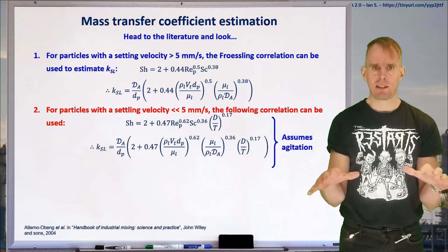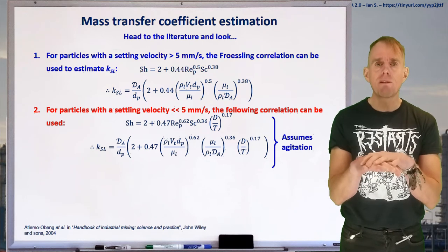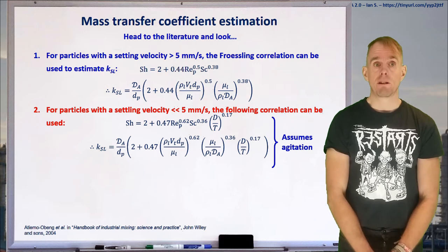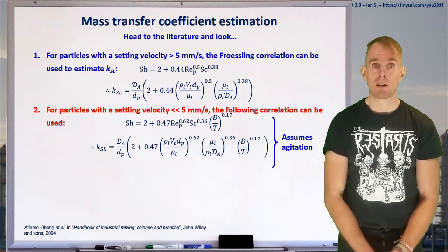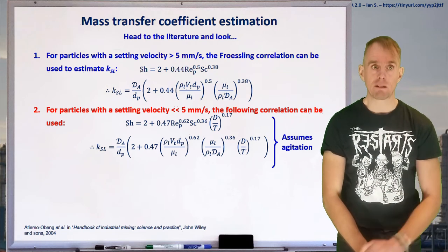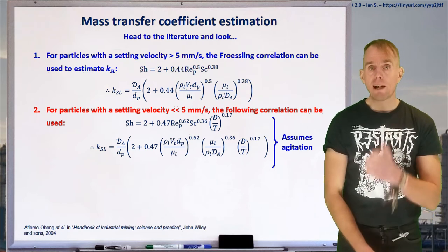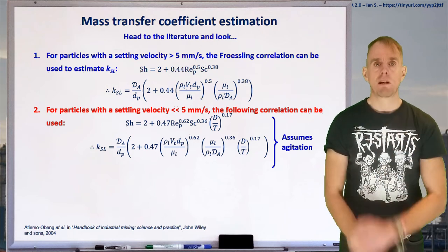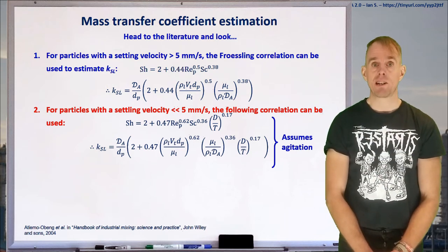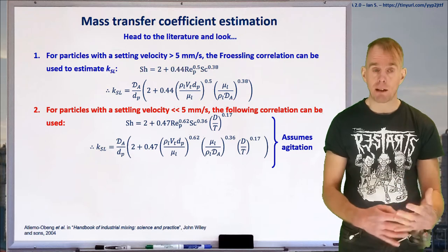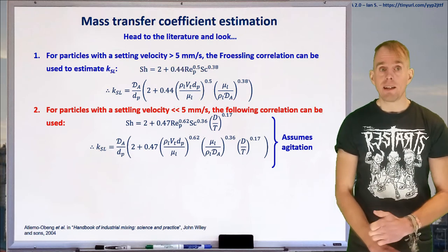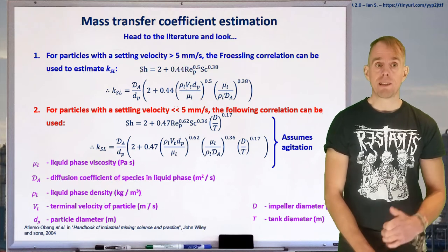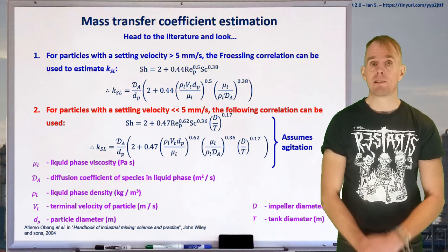If you've got very, very fine particulates that settle very, very, very slowly, then you'll need a different correlation to the Froessling correlation. And here on the board, I've put a correlation for particles that, indeed, settle very, very slowly. And we'll see that it's got an extra non-dimensional term in it, D over T. That's because some correlations assume that you have agitation happening and are only valid under those circumstances. D and T in this particular example are the diameters of the impeller and the diameter of the tank.